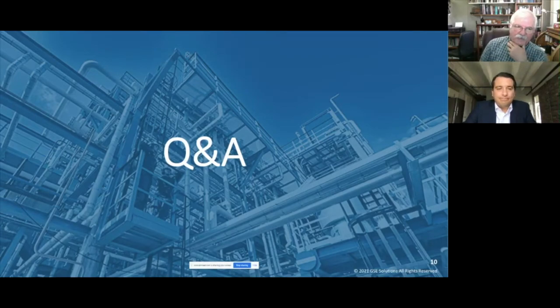That's part of the modeling process, I'll call it. Let's take, for instance, something like cycle isolation, right? We would look at that cycle. We would seek to identify cycle isolation problems when we do the modeling, and then put those into the plant. So that would be like a bias that you could have due to some leakage somewhere. So that's one of the things we do, we look at that. But part of it is the model is going to almost tell you sometimes that there's something wrong somewhere.